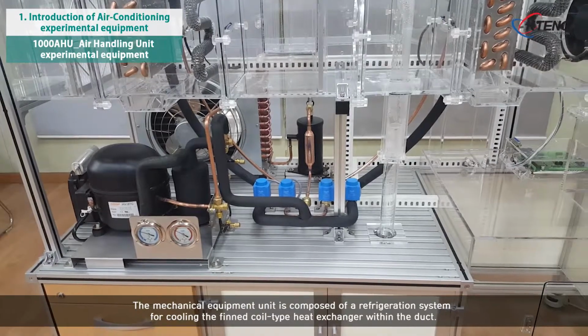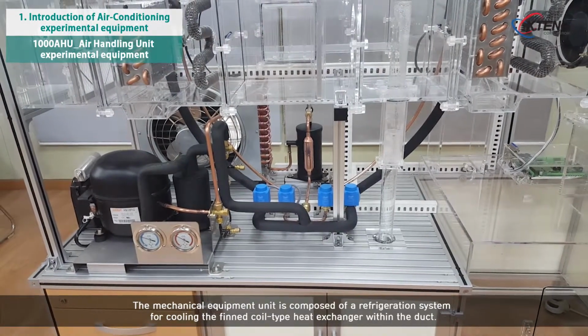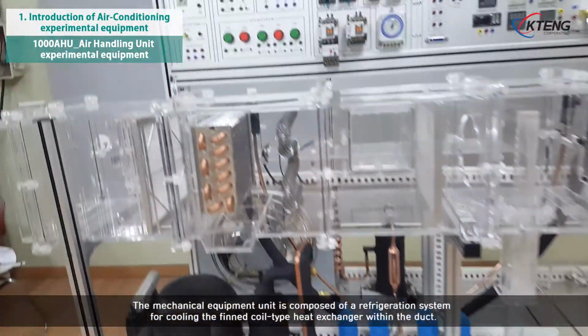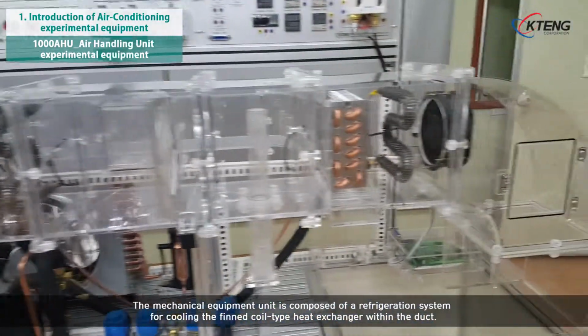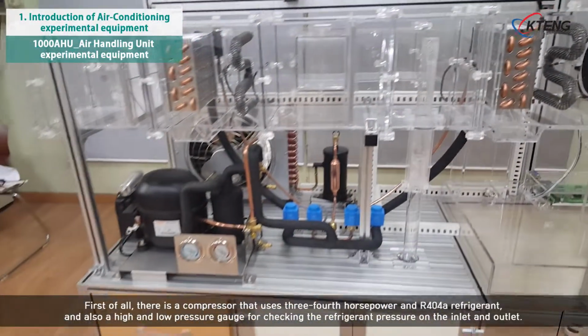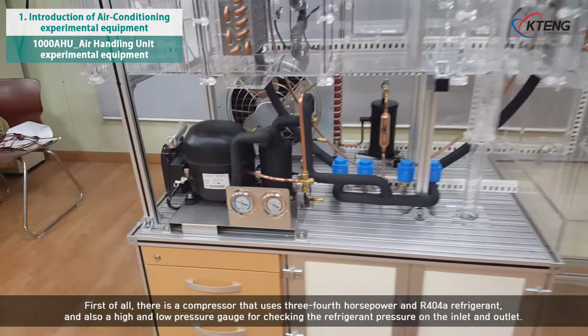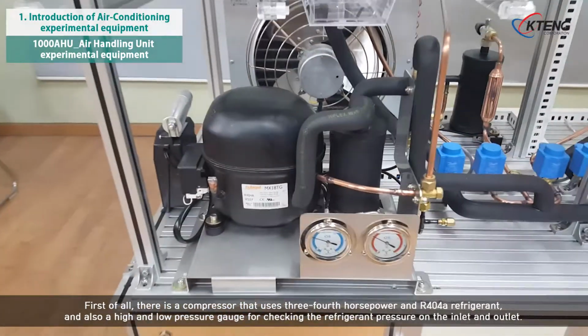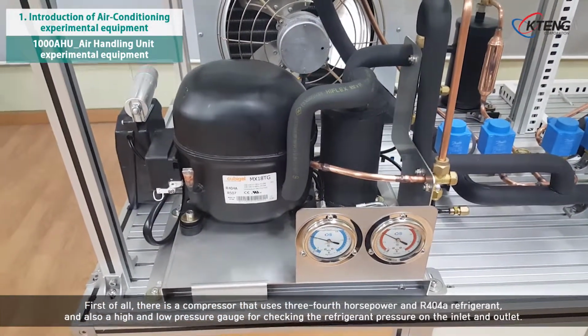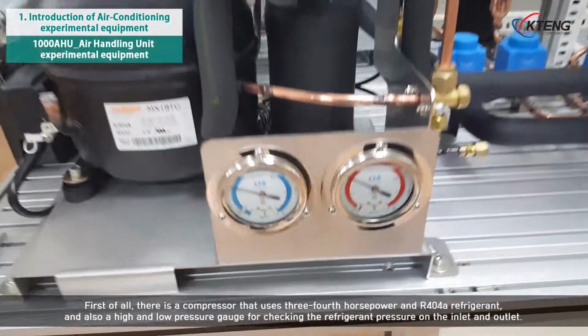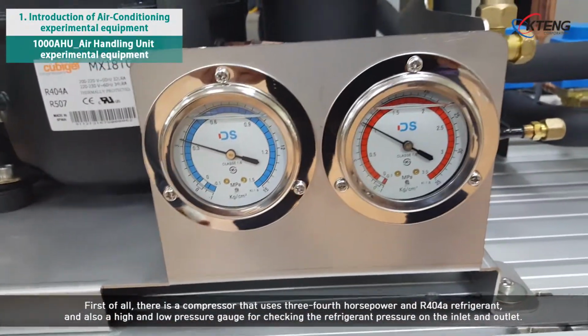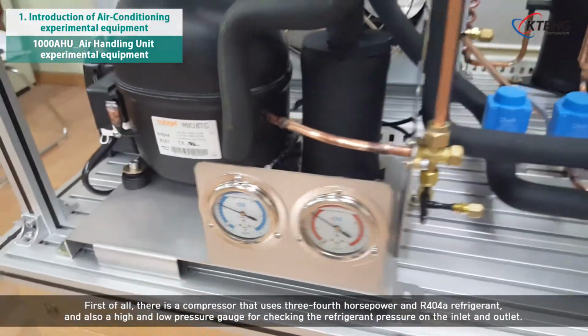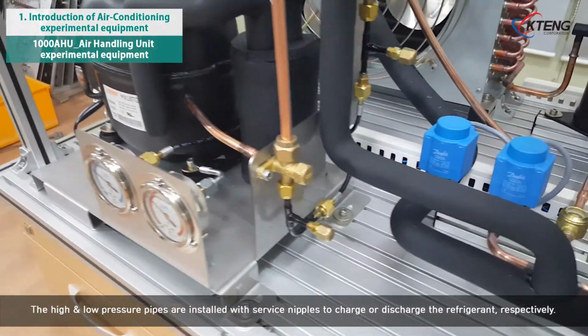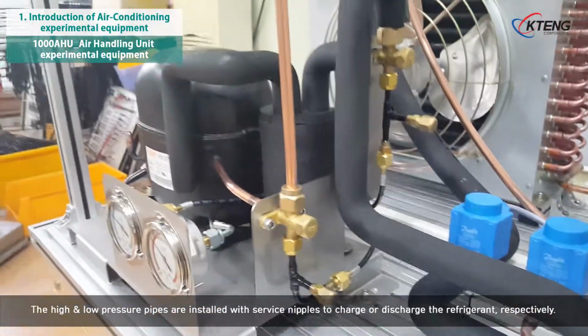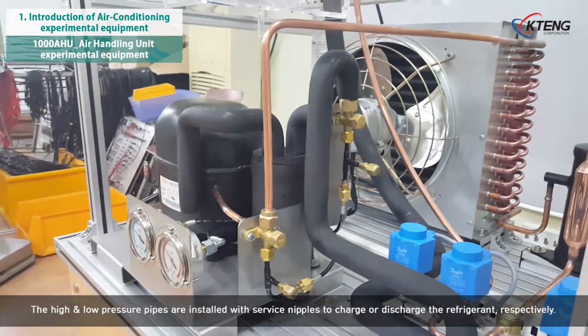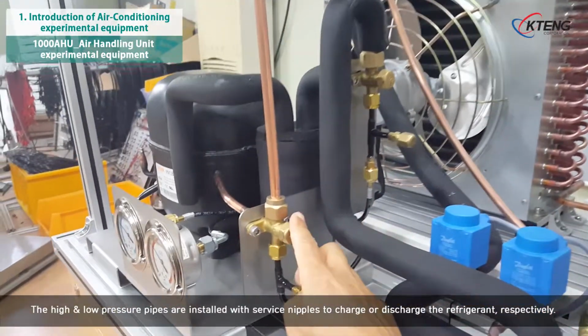The mechanical equipment unit is composed of a refrigeration system for cooling the finned coil-type heat exchanger within the duct. First of all, there is a compressor that uses 3/4 horsepower and R404A refrigerant, and also a high and low pressure gauge for checking the refrigerant pressure on the inlet and outlet. The high and low pressure pipes are installed with service nipples to charge or discharge the refrigerant, respectively.